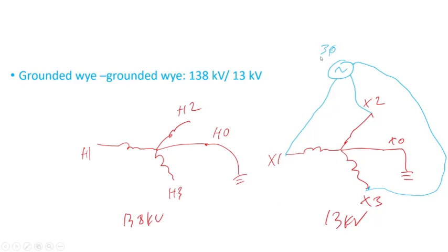In other videos I'll talk about how the induced voltage test depends on whether it's applied to a power transformer Class 2 based on IEEE designation — in that case you could do a one-hour test with partial discharge measurement. You calibrate the PD equipment, apply the test, and measure voltage, current, and partial discharge level. But this video is just about test connections.